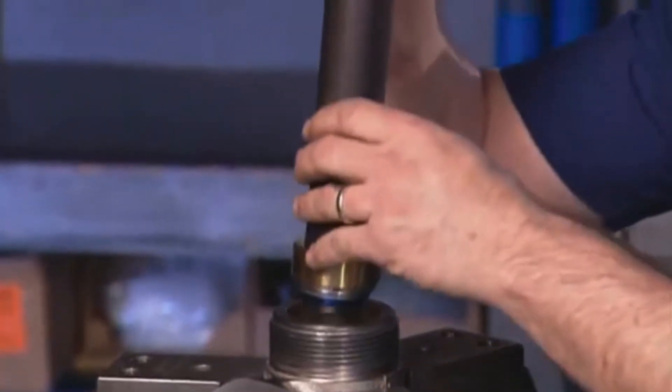Spread the bluing compound around on the disc until you've got a very uniform, thin covering of bluing on the disc. Next, insert the tool into the body, apply firm pressure down against the disc and seat, remove the tool from the body, and inspect your blue line.